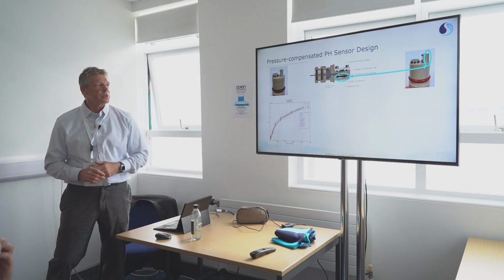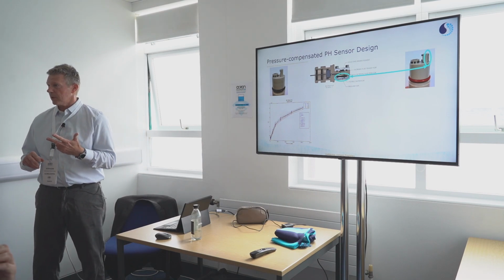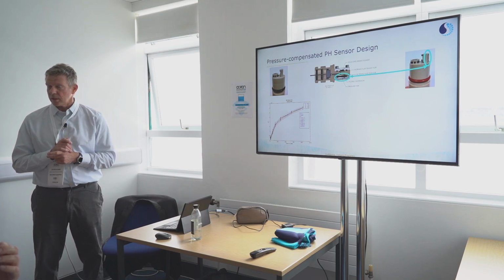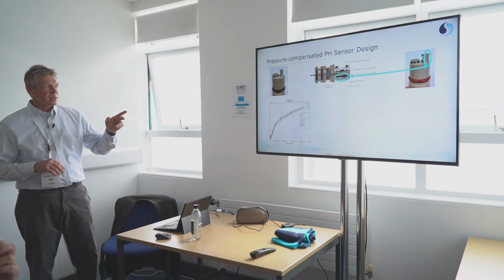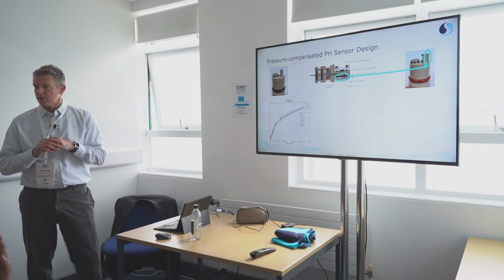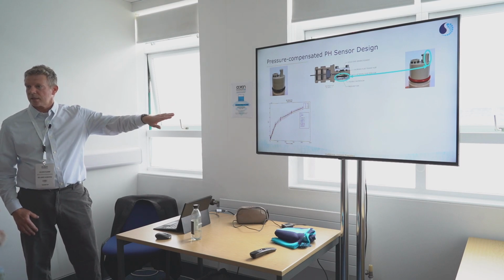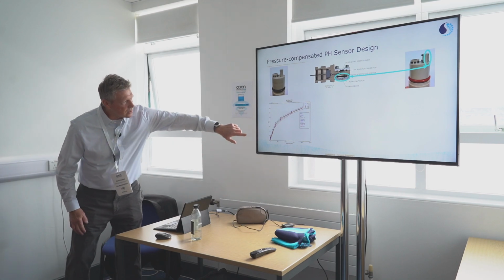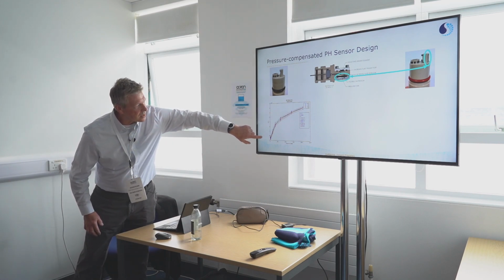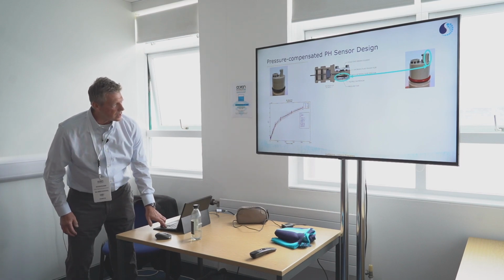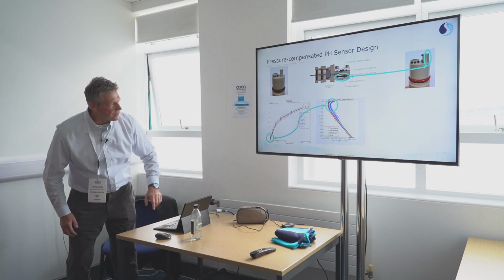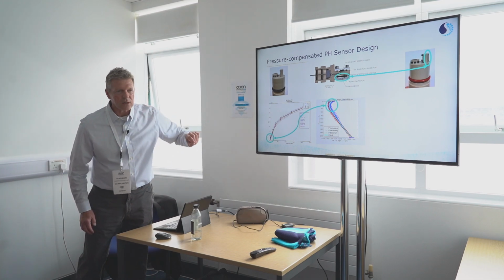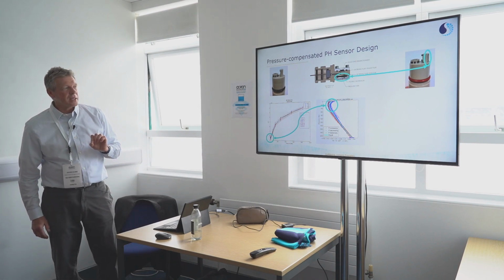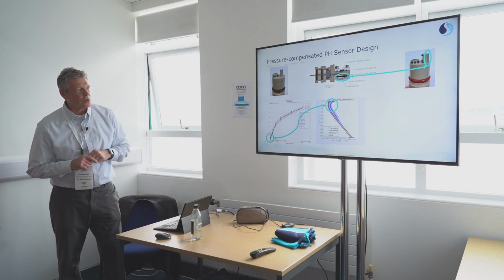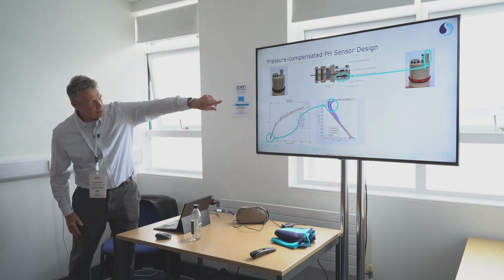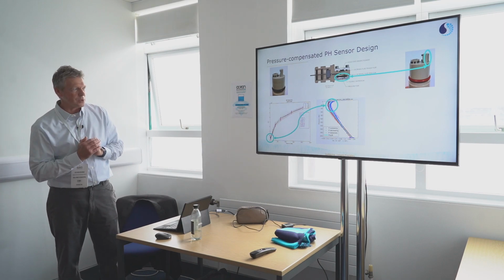If you look at how you typically calibrate, I've talked about the 3 different steps of calibration for the ISFET sensor. There's the temperature part. What's shown here is the pressure part. What you see is a fairly nonlinear calibration, a nonlinear response of the sensing element to pressure. And this is for the original design that's not pressure compensated. So you can see here it's not a very linear response as a function of pressure. One thing you don't see in here is that there's an area very close to the surface that is not well modeled currently. So even by increasing the resolution on the pressure steps that you do, you should see on the middle plot, although you have to rotate it by 90 degrees because we changed orientation here.